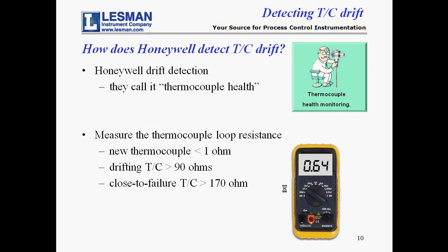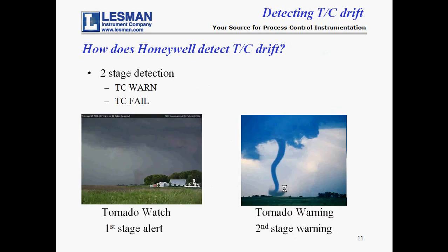Although there's no means to correct for drift, there is a method to detect thermocouple drift. Honeywell controllers detect thermocouple drift and provide two-stage alarming. Honeywell calls its method thermocouple health monitoring. The actual detection method involves measuring the resistance of the thermocouple input circuit. A new thermocouple has a resistance of less than an ohm. A high resistance measurement indicates that a thermocouple is drifting, and even higher resistance indicates that the thermocouple is near failure. The controller's drift detection provides two-stage alarms: TC WARN and TC FAIL.